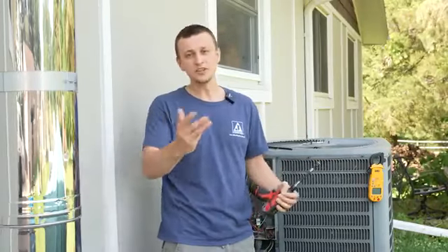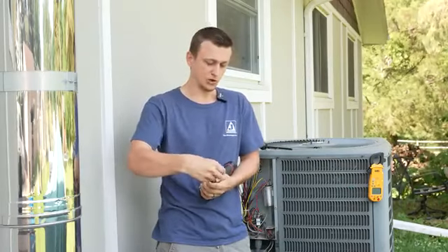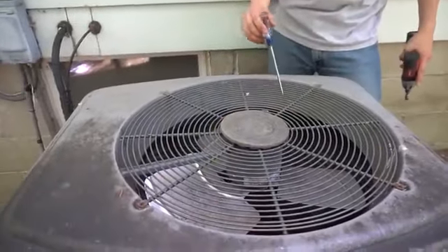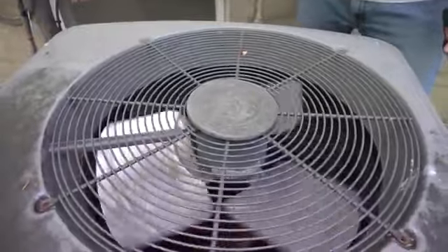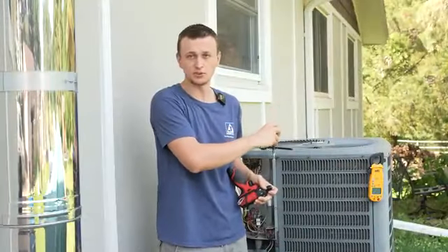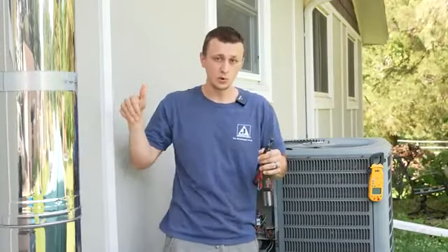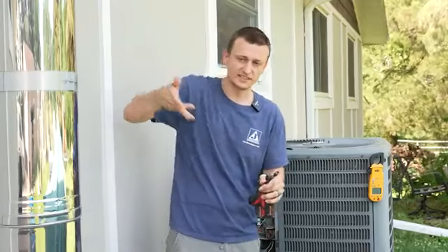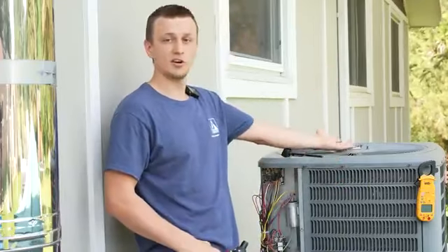And to do that, all you need is just a long stick or maybe a long screwdriver. You could even use like a drill bit extension like this. You reach in between the grates and you just give that fan blade a push, just to get it going. As the unit is running, you should be able to hear the compressor running when this is happening. And the direction that you want to push the blades is so that the blades are facing downwards. So whatever way you're pushing it, make sure the blades are scooping the air, so they're facing down the direction that they're going into. You want the fan to be pushing the air up.